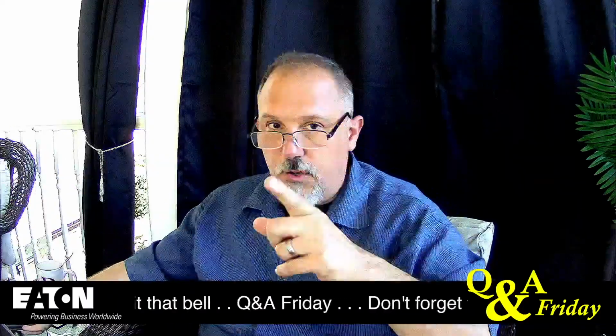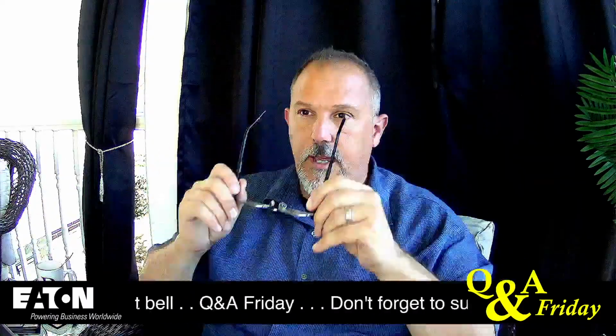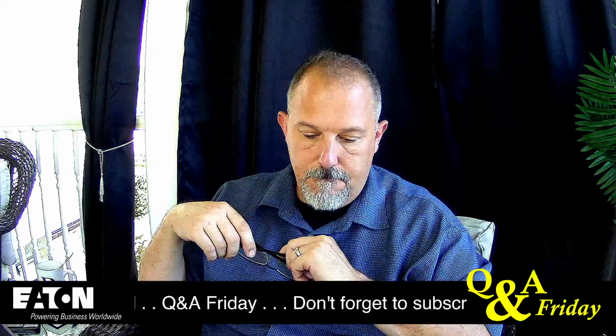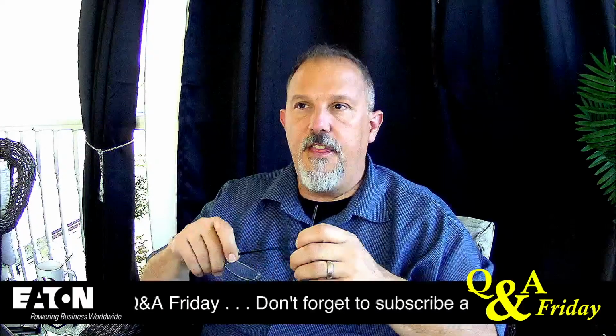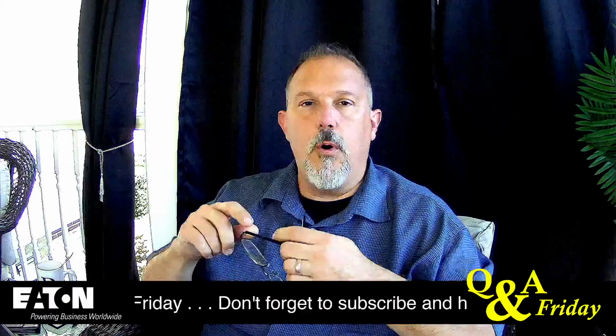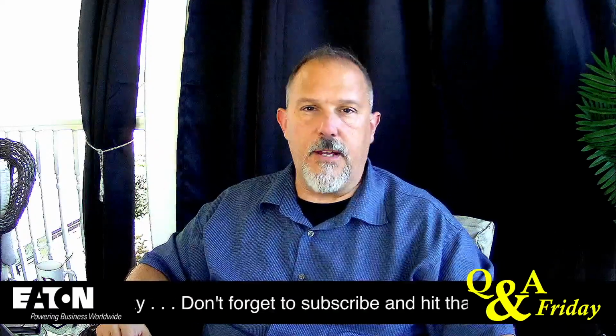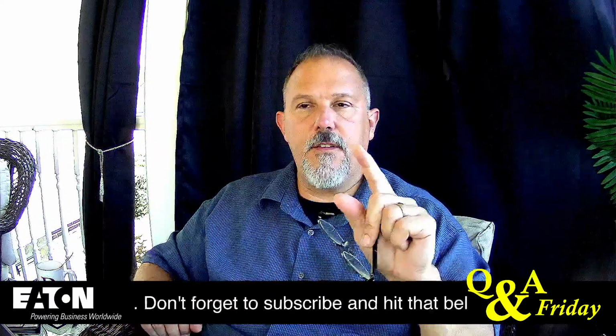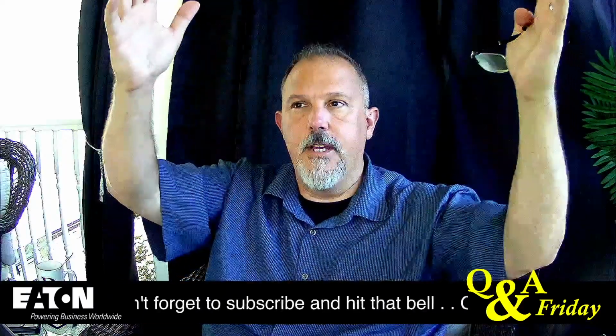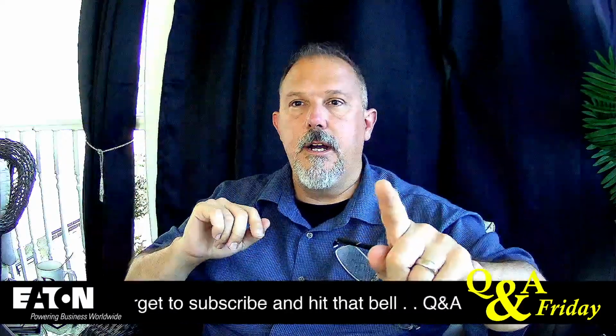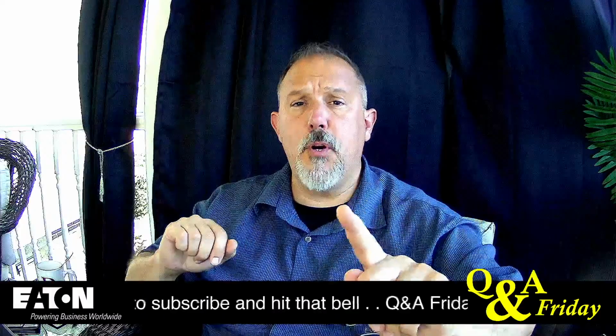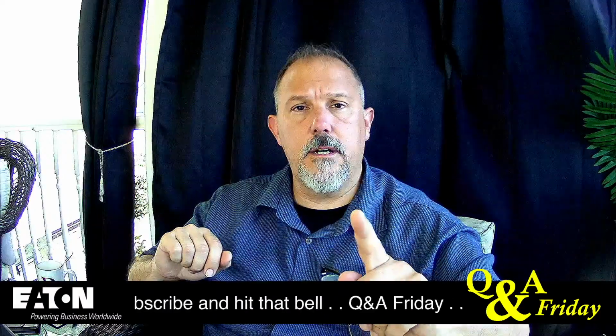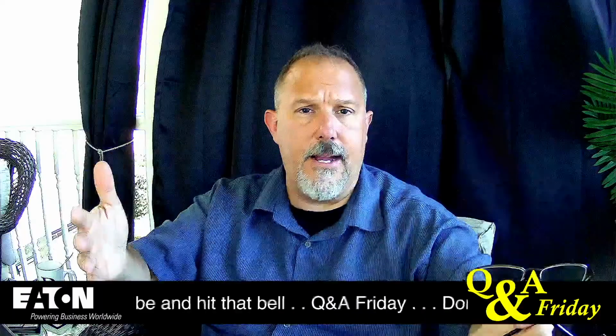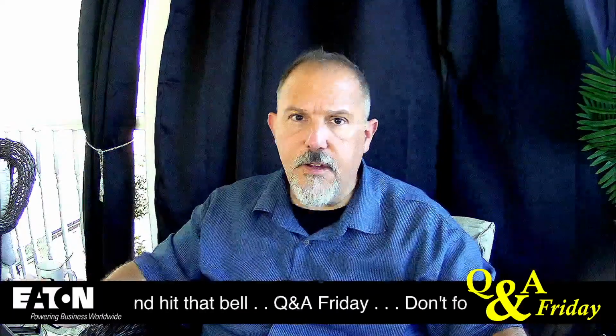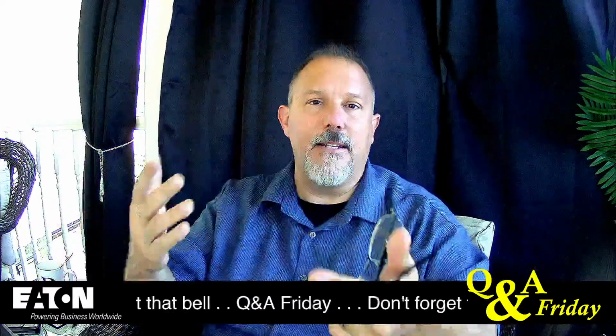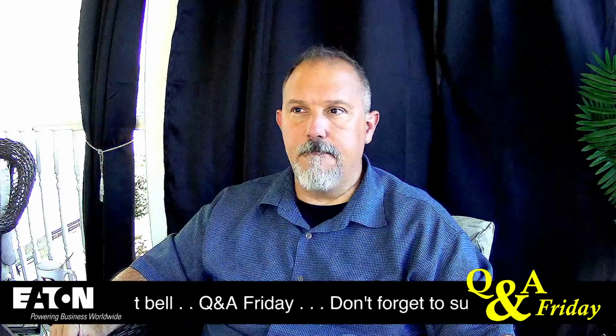You have two things. One is you can say that you won't have line side propagation, or you will have line side propagation. Say, for example, you put a barrier in there and you say, look, I've barriered this, and I have no exposed electrical contacts, electrical pieces or parts. That line side bus is barriered off. I can't touch it. I can't accidentally hit it.